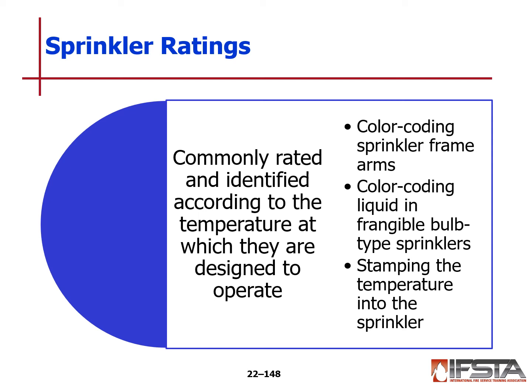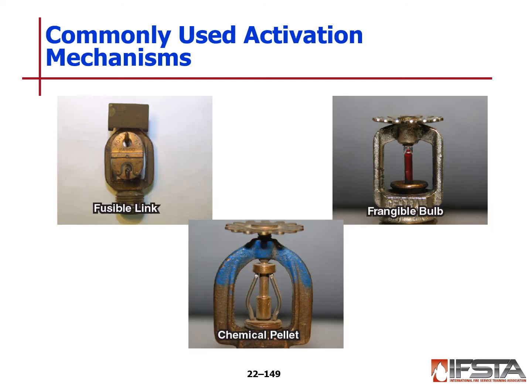Sprinklers are commonly rated and identified according to the temperature at which they are designed to operate. Oftentimes there is color coding on the frame and the arms of the sprinkler. The color coding in liquid filled could be the color of the glass bulb that the liquid is in. There is also stamping of the temperature into the sprinkler, the arms, or the head. Here's what some of them look like, commonly used. On the top left is the fusible link. Basically there's a link in here that is set to melt at a certain temperature, and when it does, it will cause the arms to fly apart because that's under pressure. You've got a little bit of water pressure there at the base, and then it will begin to flow water.